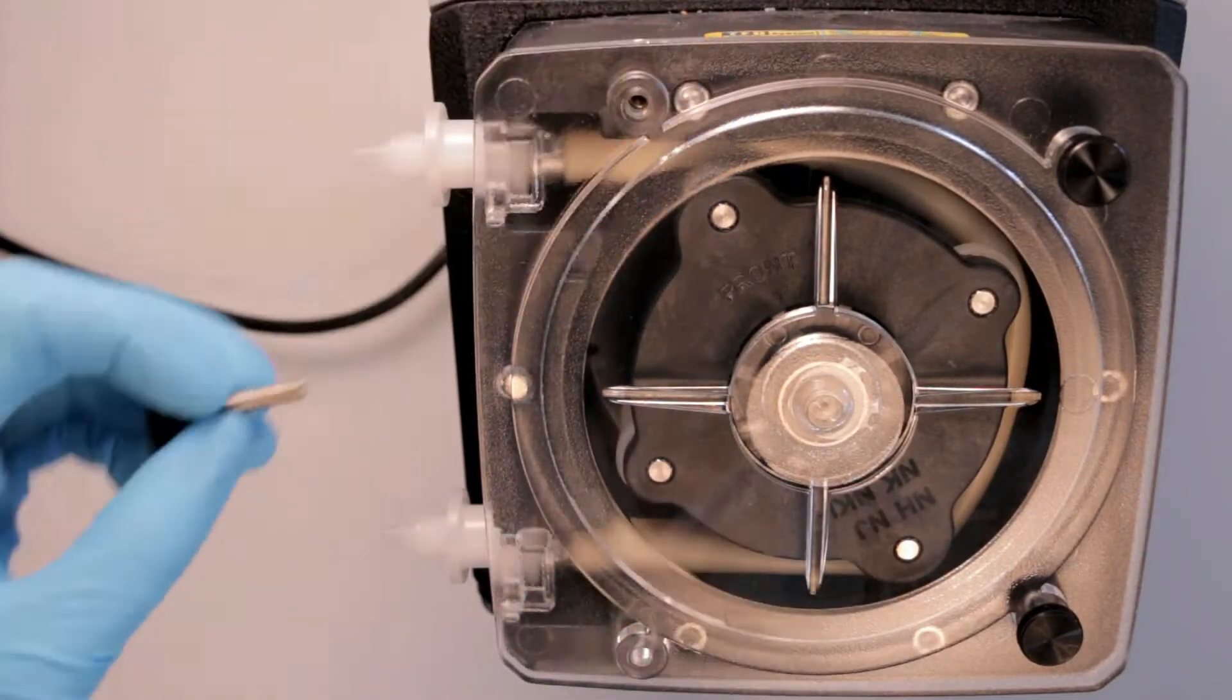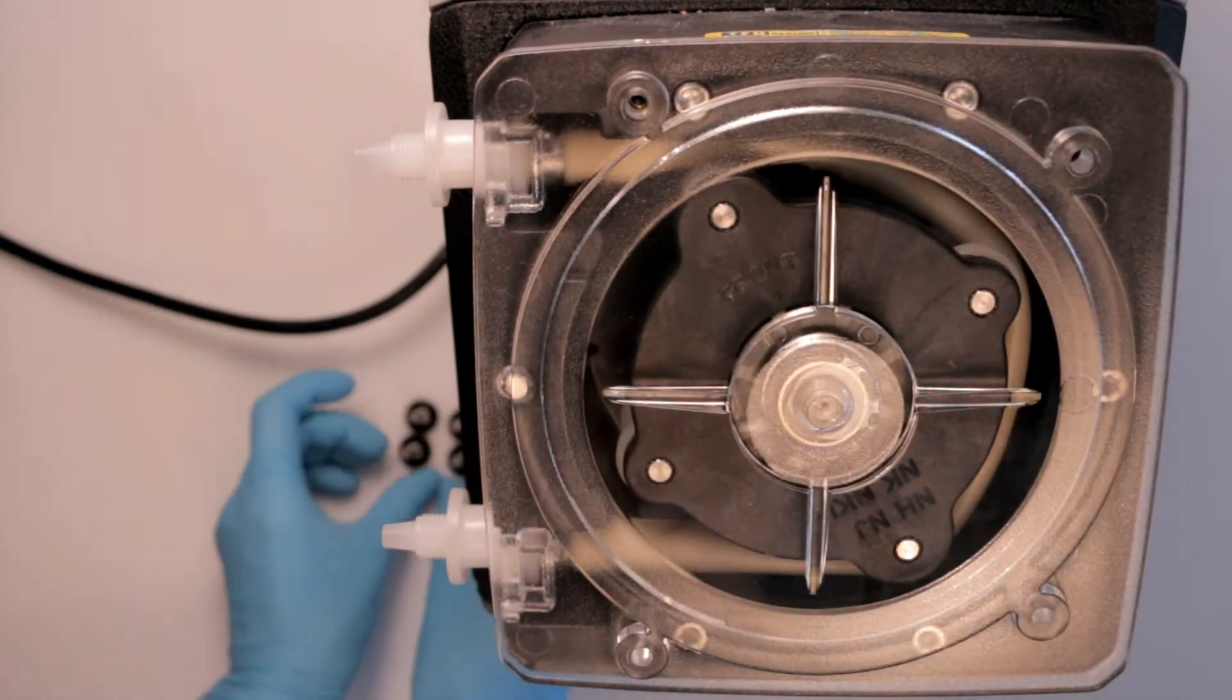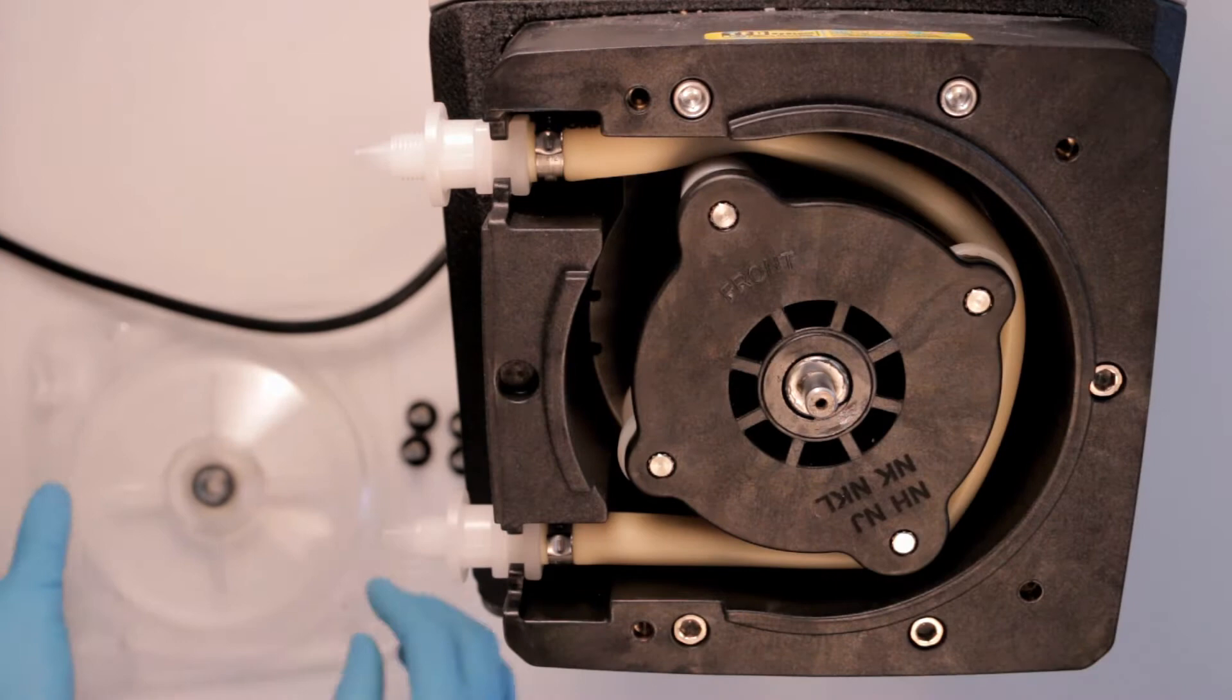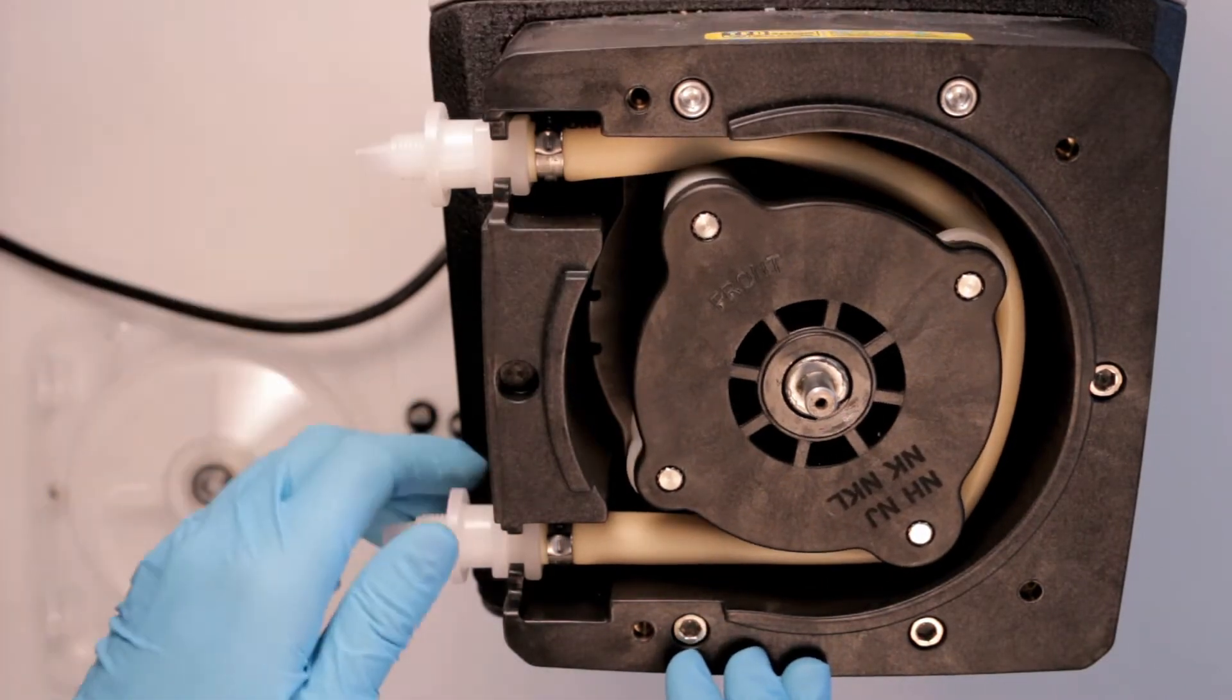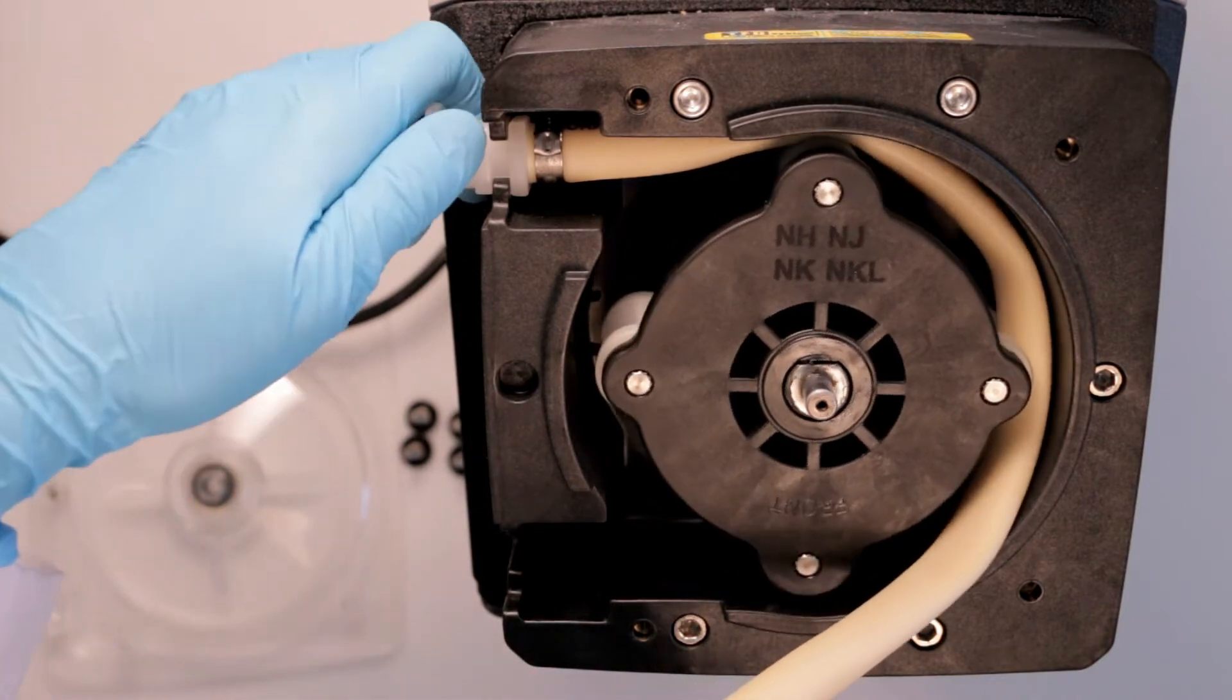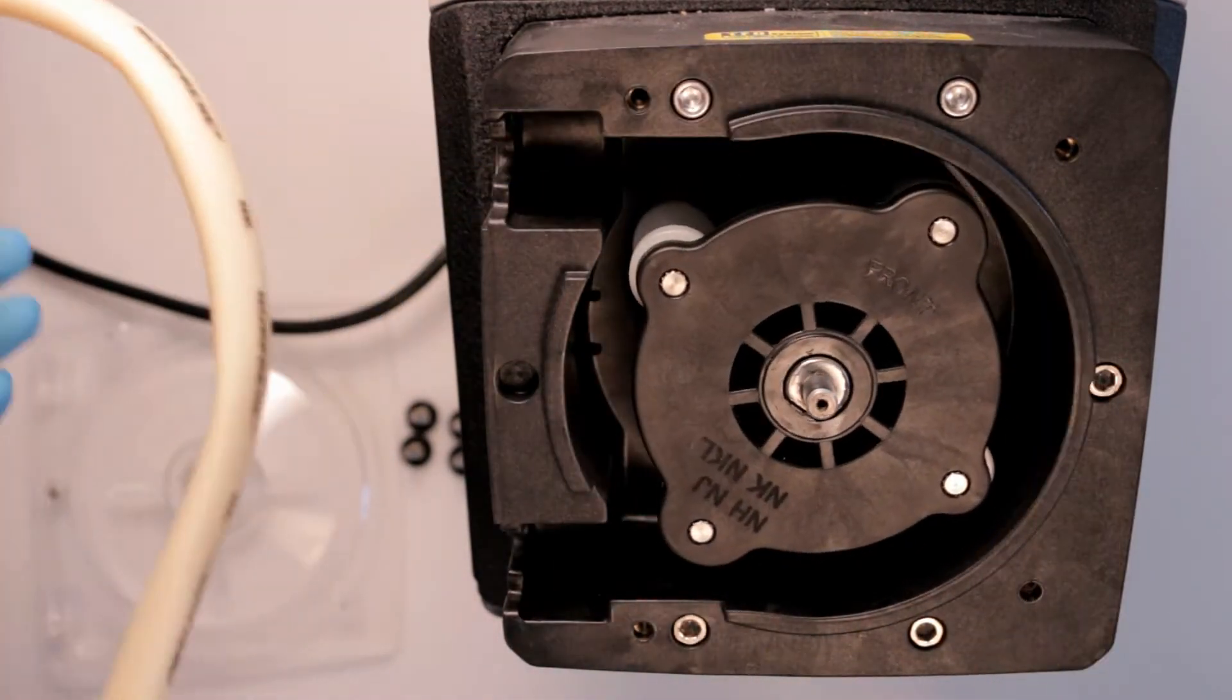Remove the pump head cover. Press the start button to have the pump initiate a slow rotor rotation. This is called the maintenance mode. Once you've removed the tube assembly, press stop.